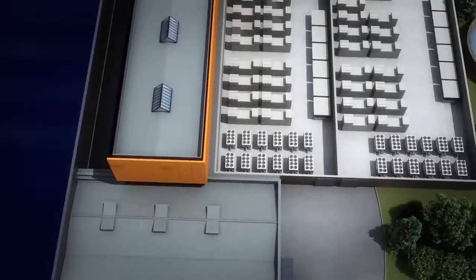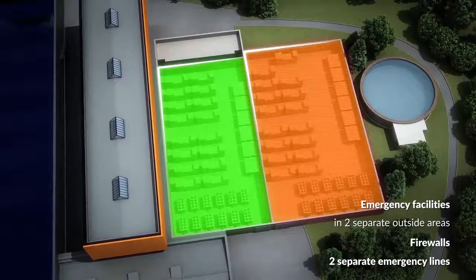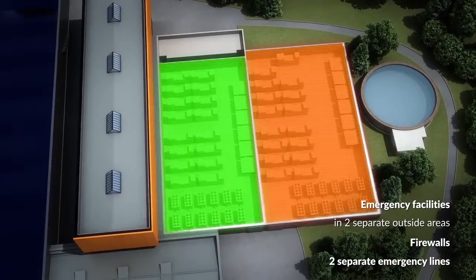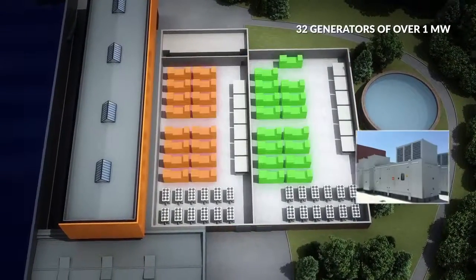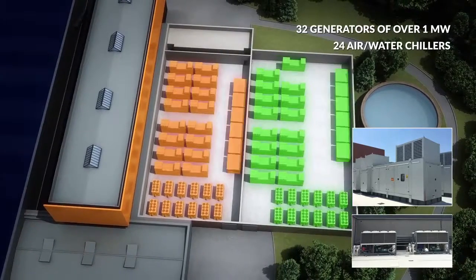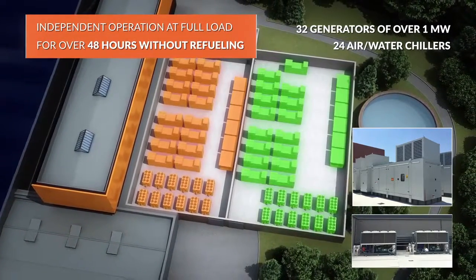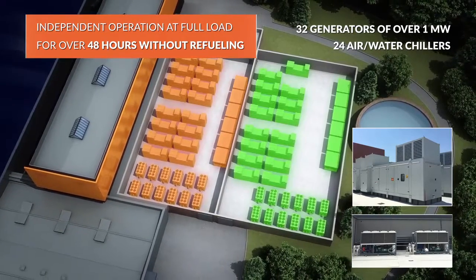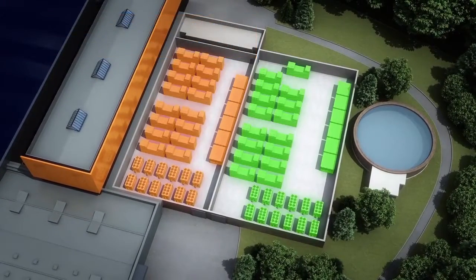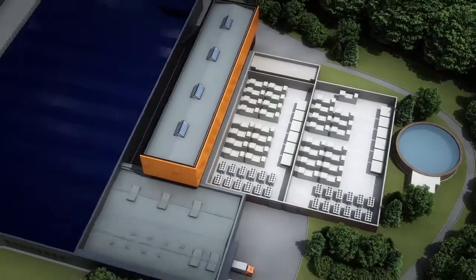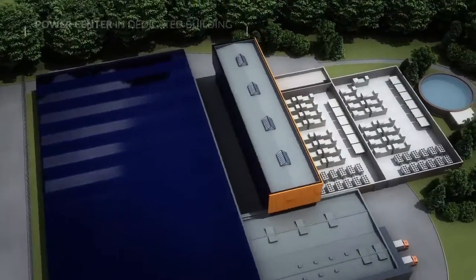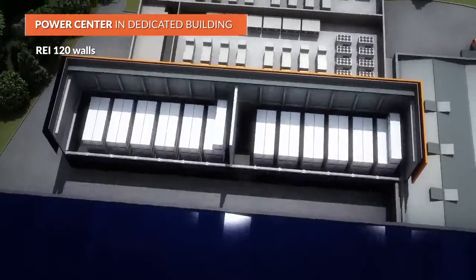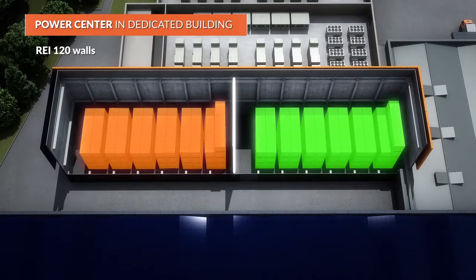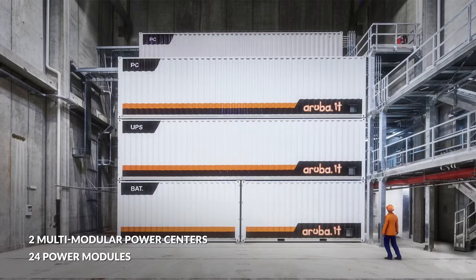The backup installations are located in outside areas, each corresponding to an independent supply line. Each space contains diesel generators, backup air-water chillers and fuel tanks that provide for 48 hours of independent operation at full load without refilling. The double power center is separate from the data center and is made of reinforced concrete. A firewall divides the building into 2 units, corresponding to the 2 power lines. Each of the 2 rooms is designed to contain the modules required to power the 10 data rooms.